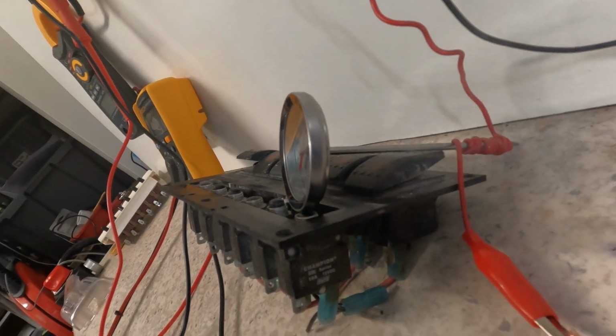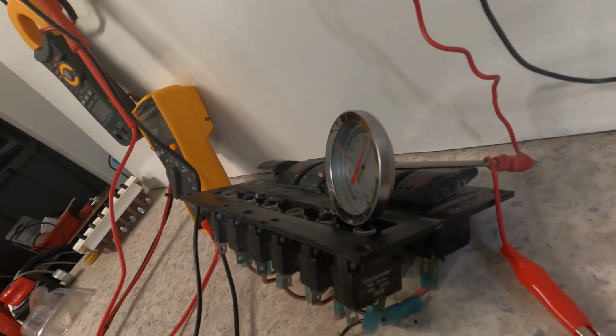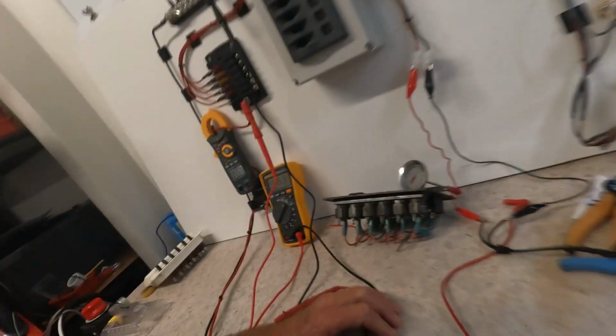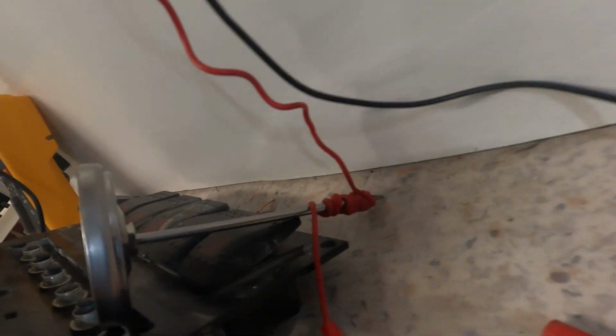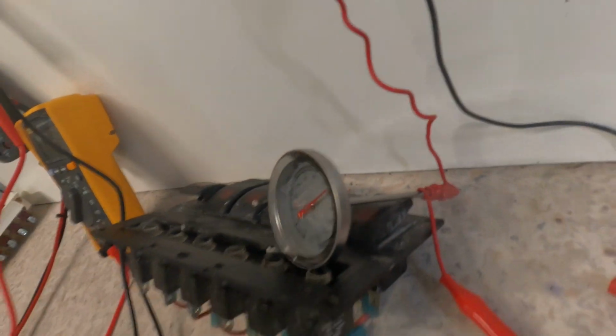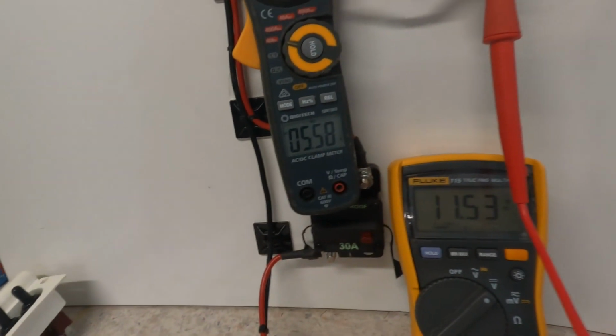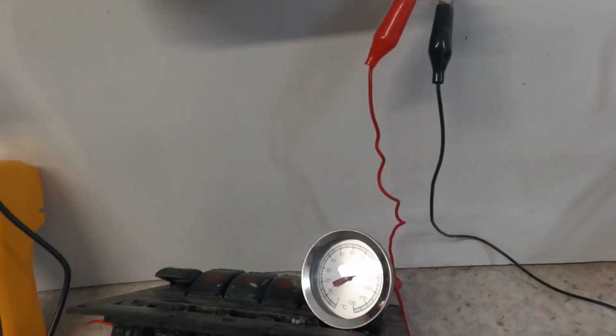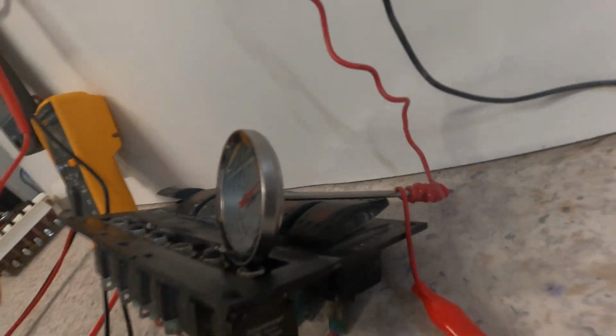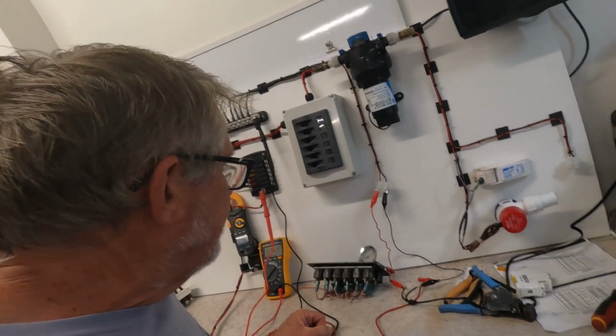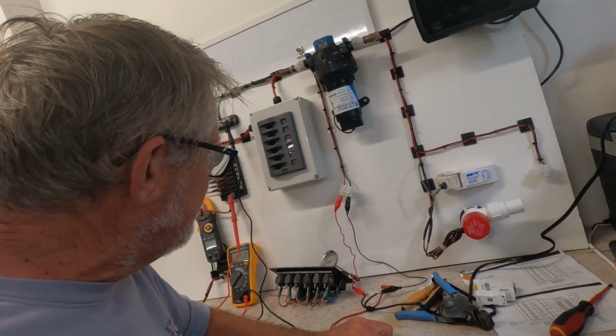Starting to go. What I want to do is prove something else to you, and it will in a second. If we get right up close, have a look at what it's doing now - yeah, I should probably have a mask on, this is starting to suck in that smoke. So that's only at 5.5 amps with a tiny little wire, and the insulation on that cable is starting to melt.